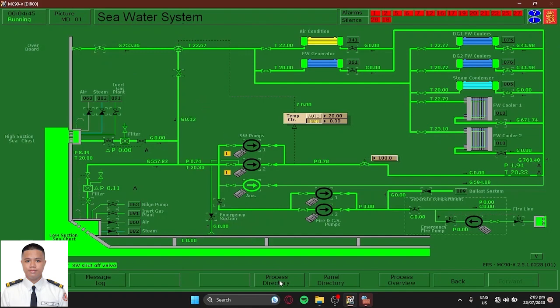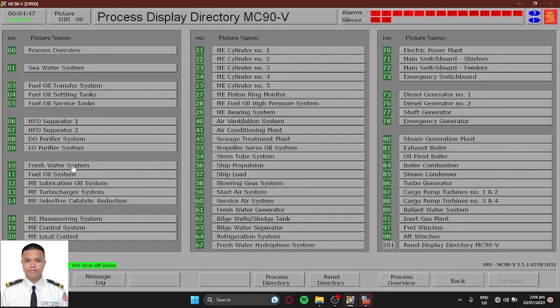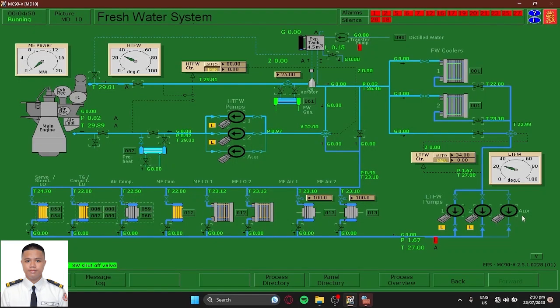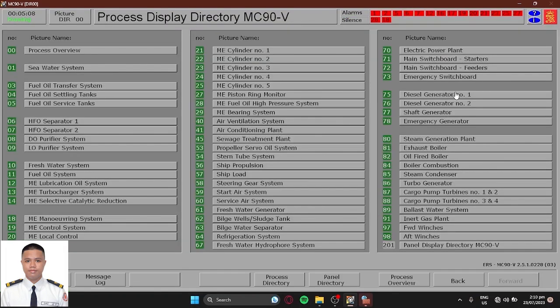Next is to go freshwater system. Number 10, freshwater system. Let's go here. Open the auxiliary pump. Open this compressor valve, air compressor valve. Open this valve here and the freshwater valve 1 here. And this bypass valve. So we have already satisfied our cooling system. So let's go back to diesel generator 1.